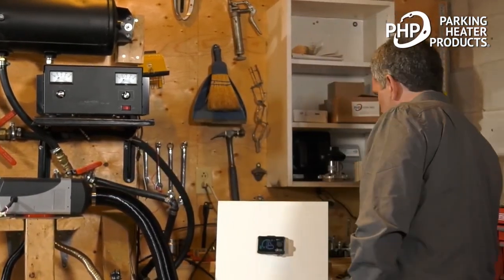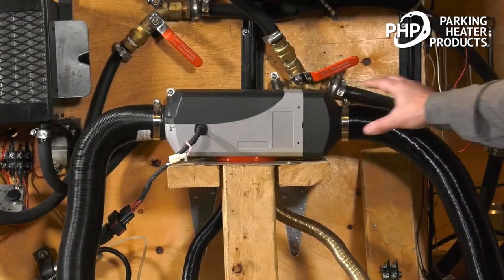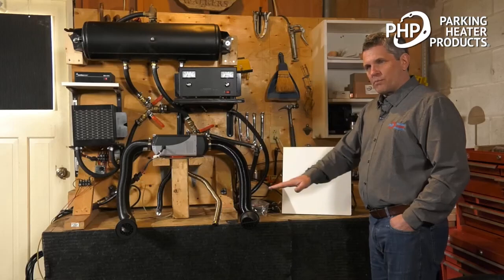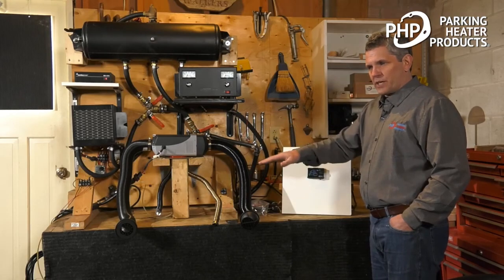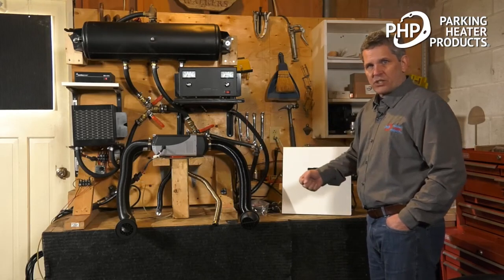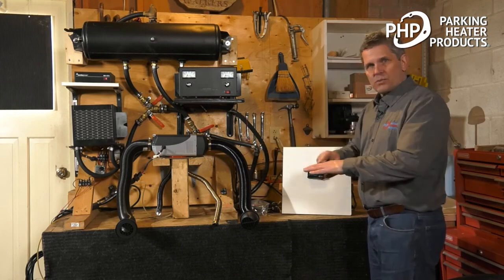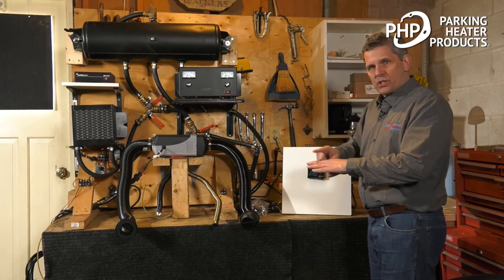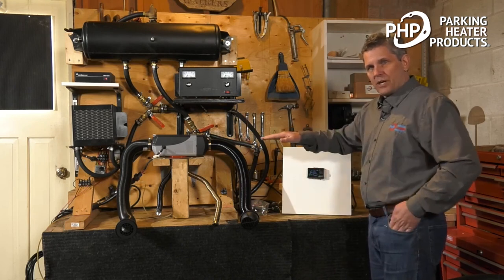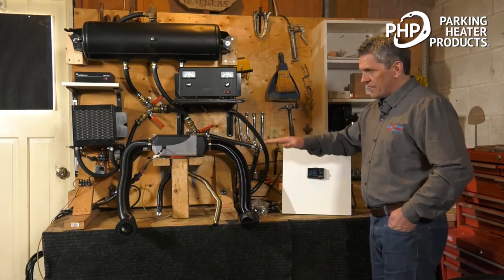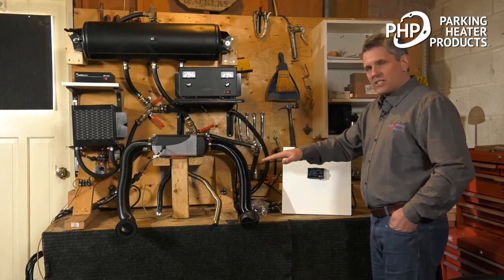In this mode, the heater is going to regulate and the blower motor is going to speed up or slow down, bringing in the different combustion air, and the fuel pump pulses will speed up or slow down to maintain a fuel-air ratio, but it's going to maintain a nice even temperature.